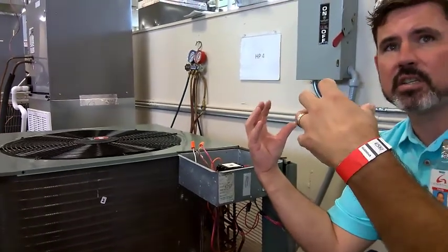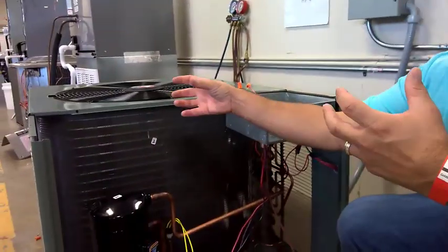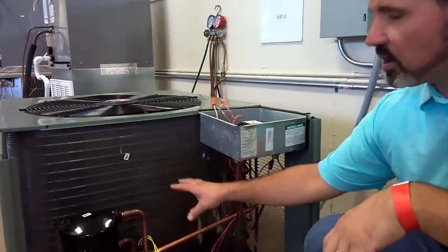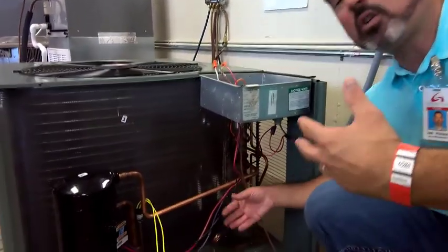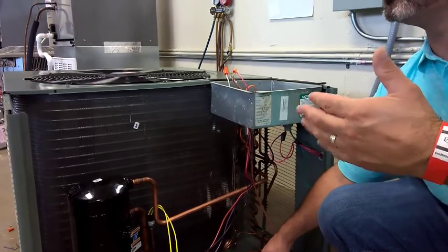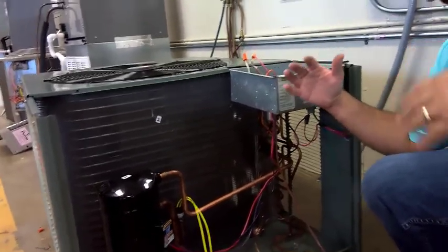That's our saturation point. So it comes out as all vapor, it's superheated. It's above that point. Once we cool it off into a liquid and keep cooling it off, it comes out of what we call subcooled. So it's cooler than that temperature that it changed states. All right?